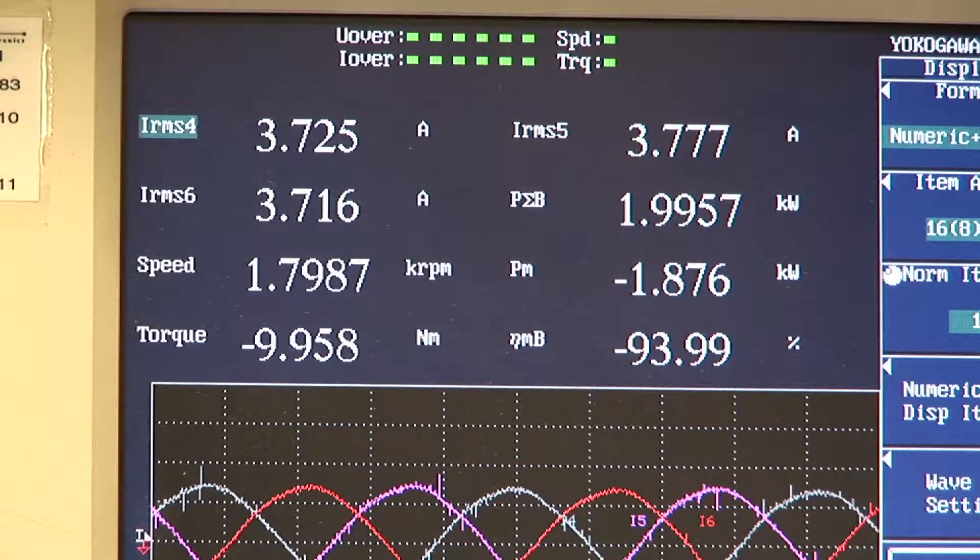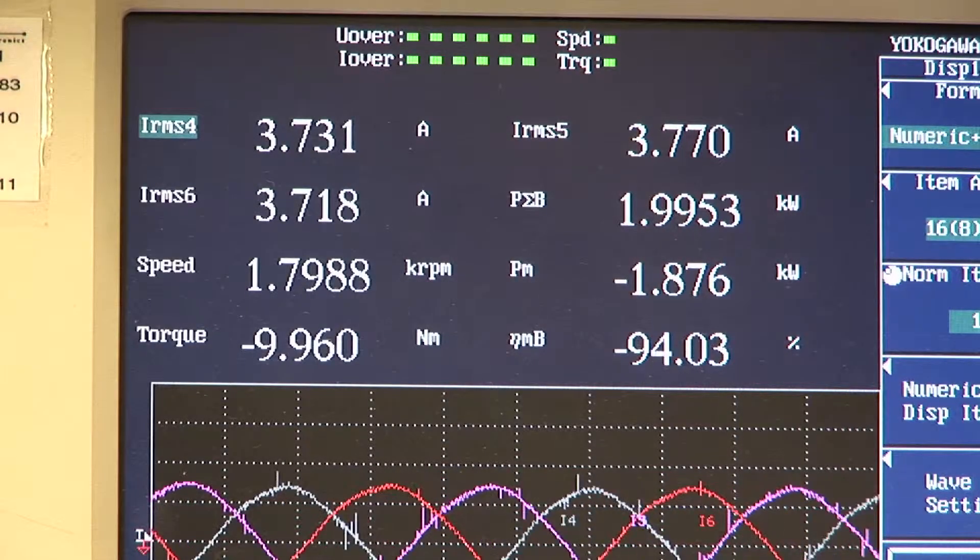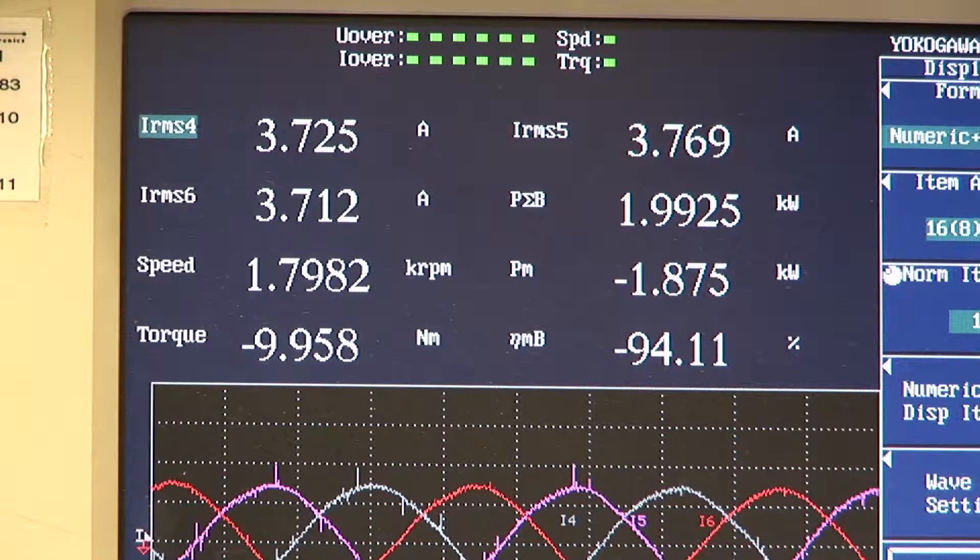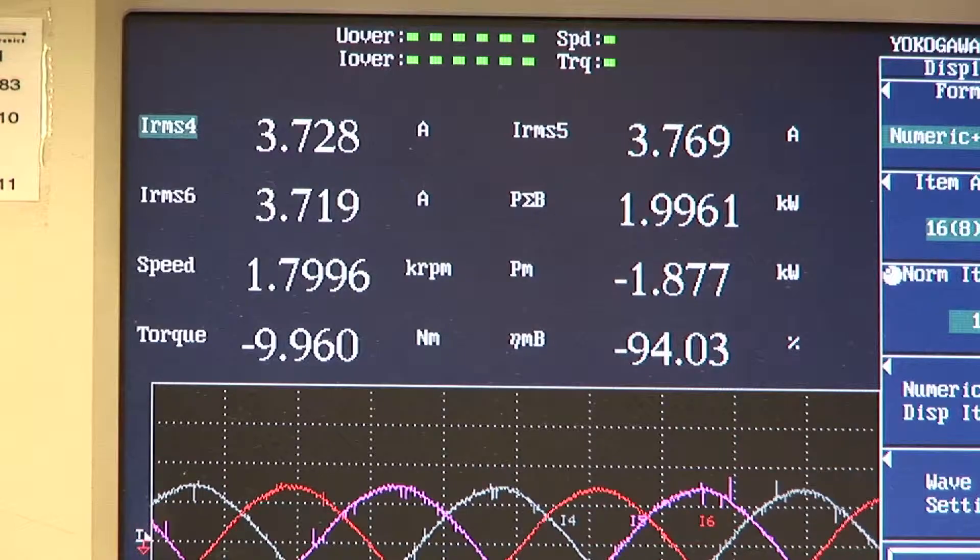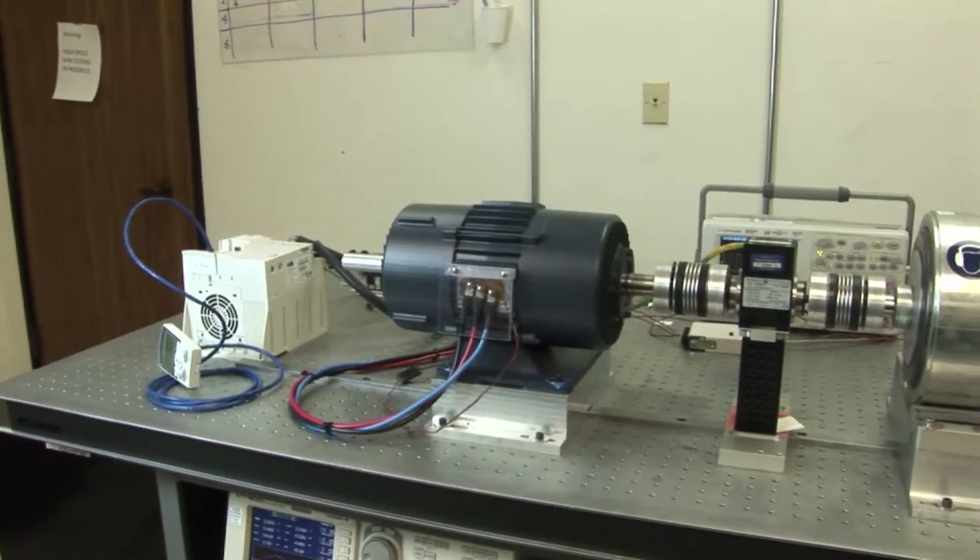We are now running at the rated speed of 1800 rpm at half the rated torque, that is 10 Newton meters. The premium plus motor's efficiency is almost hitting 94 percent.